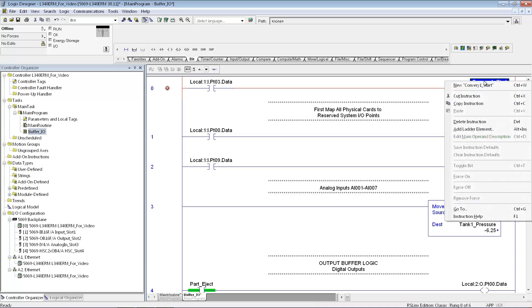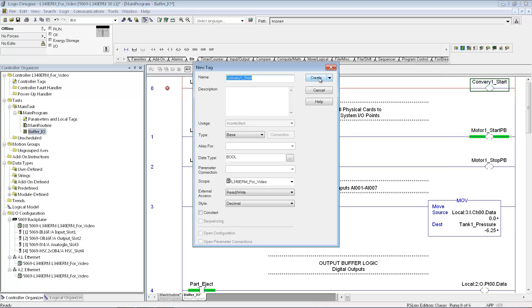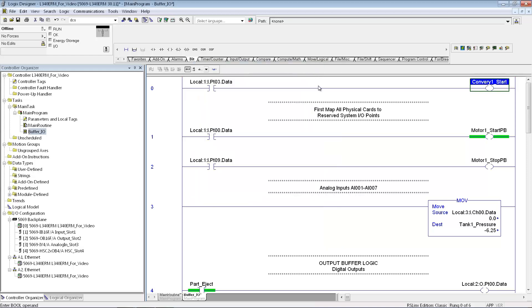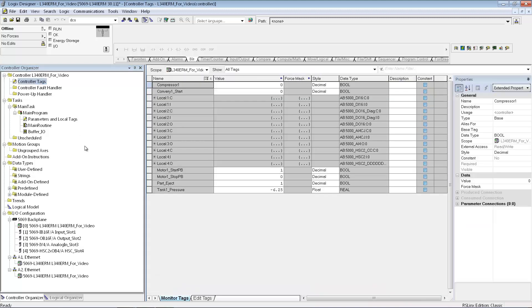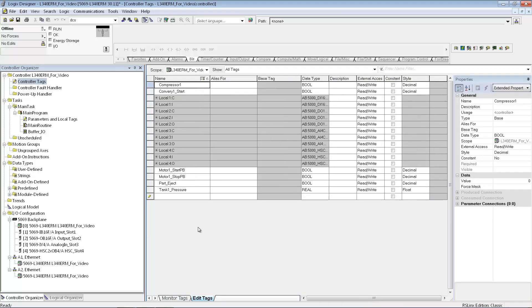So if I'm making this tag, it hasn't been created yet in my controller, so I need to right click on that, and then it'll say make a new tag, so it's new conveyor one start. It's just going to be a boolean tag, and I'm going to say create that. I can create tags in a number of different ways. This is an easy way to do it as you're going along with your programming, and the other way to do it is you can go into your controller tags here, and these are all global to your processor, and just edit tags here and create them all ahead of time if you'd like to do it that way as well.